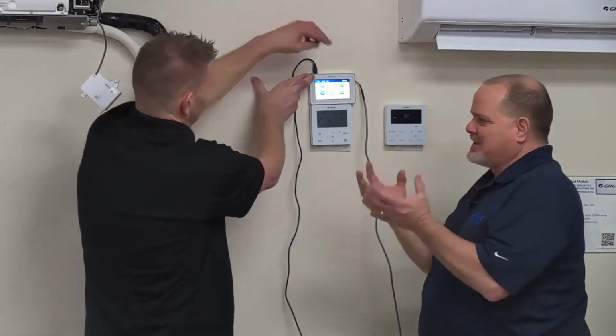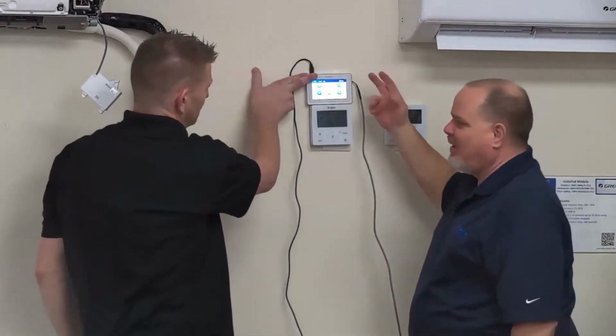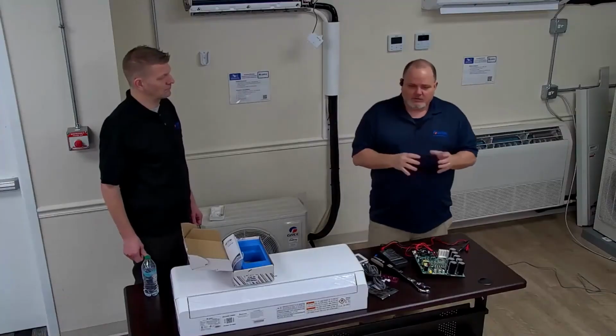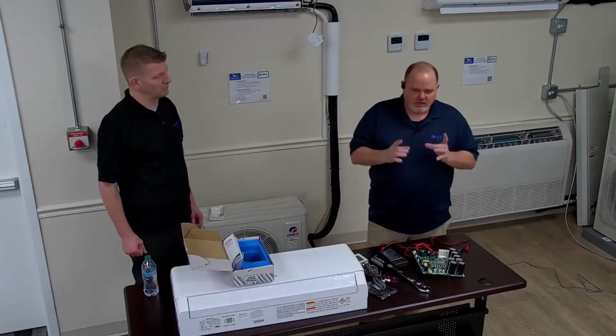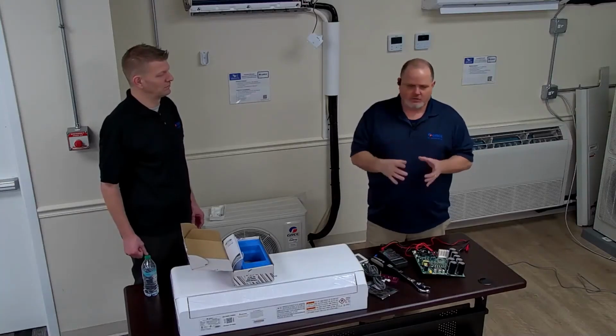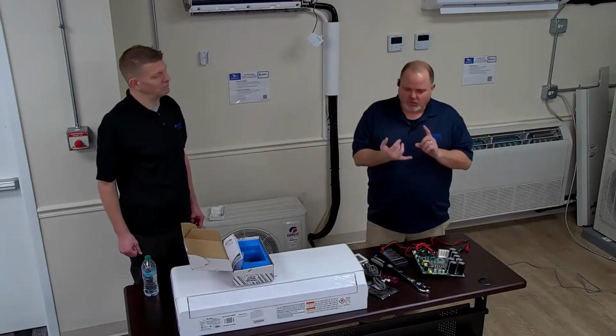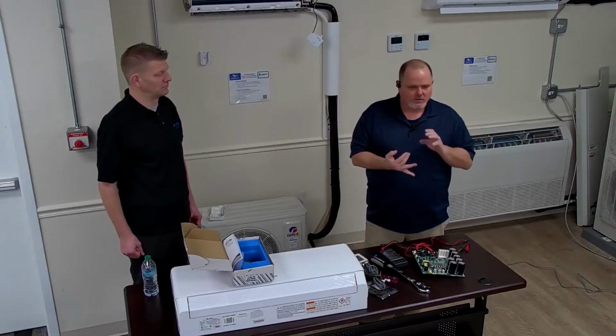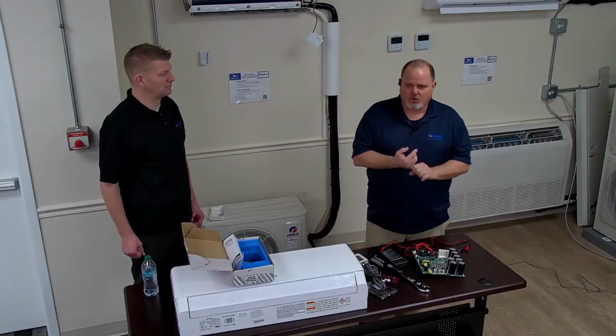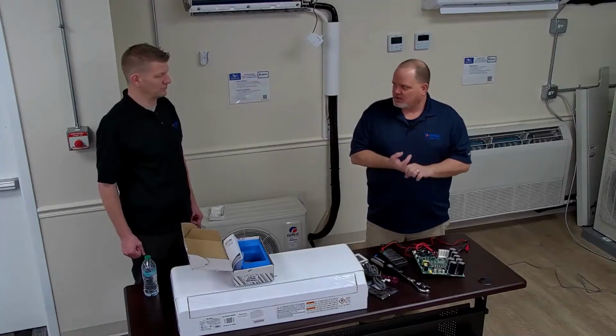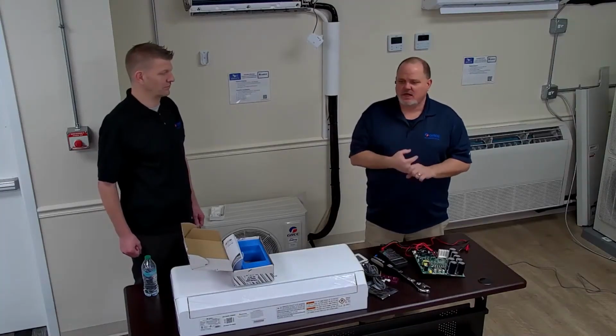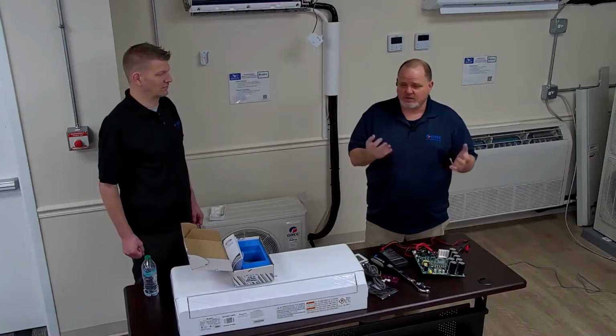All we want to know is, is that EEV wide open? Is it not wide open? All I'm trying to tell you guys is the service tool gives you what you need to know to figure out what's going on with that machine. You don't have to hook gauges up to it. You don't have to do a whole bunch of thermistor readings and stuff like that. You can go to the indoor unit status and look at the indoor ambient, and if it says it's 68 degrees, is it 68 degrees? If it's not 68 degrees, if it's 85 degrees in there, then we need to dig into that indoor ambient thermistor, right? Right. Oh yeah.